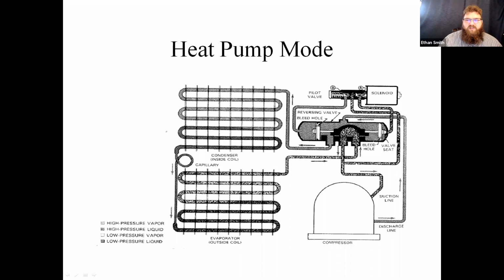So what they use is a pilot valve. Like I said, there's actually another capillary tube that comes off of the high side discharge of this compressor and comes into this pilot valve. That's not pictured here. But you'll notice that there are some seals on either side of this clamshell. It rides on an armature here, and it's got seals inside this big valve body. And that discharge line is carrying high pressure gas off the compressor. It comes up and pipes that high pressure gas into this pilot valve, and the pilot valve is built very much like the main reversing valve.